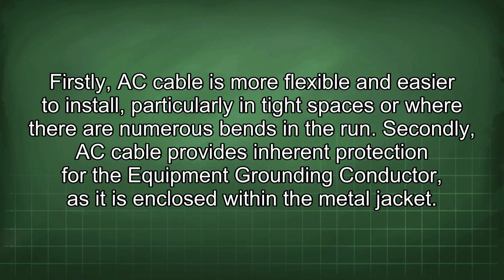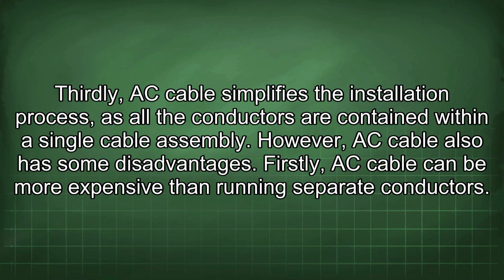Firstly, AC cable is more flexible and easier to install, particularly in tight spaces or where there are numerous bends in the run. Secondly, AC cable provides inherent protection for the equipment grounding conductor as it is enclosed within the metal jacket. Thirdly, AC cable simplifies the installation process as all the conductors are contained within a single cable assembly. However, AC cable also has some disadvantages.